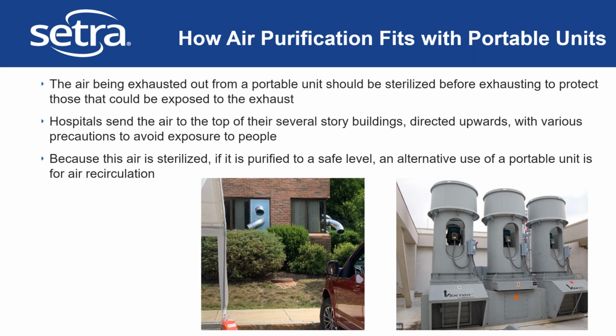You may be thinking, well, isn't that air contaminated? The way hospitals handle the negative pressure exhaust leaving an airborne infection isolation room is they send that exhaust all the way up to the top stories of their buildings, with extensive venting setups designed originally with the hospital. That's directed up into the atmosphere with various precautions to avoid exposure to people, even for someone working on the roof, with signage and barriers so people aren't exposed to that contaminated air. However, in more practical situations, like a medical office building or any other space where you're considering negative pressure, you need a more practical way to exhaust the air.